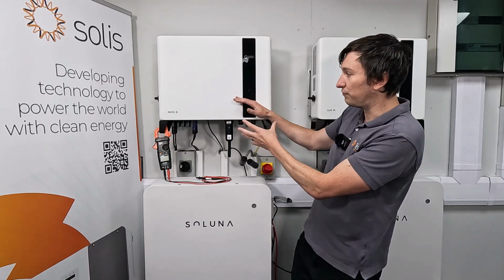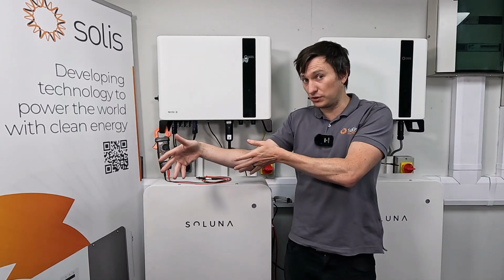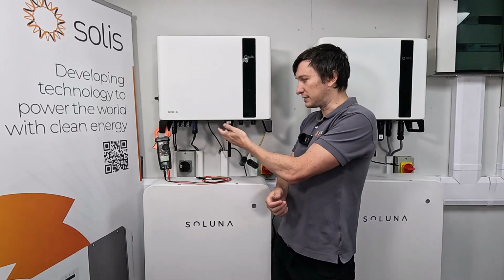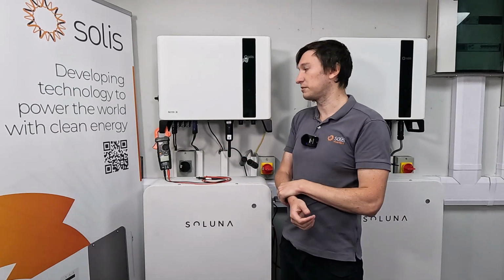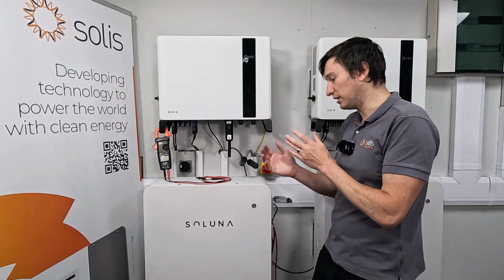The inverter is off, right? If I had a completely off-grid system where I couldn't get AC voltage, and the sun wasn't shining because it was nighttime when I installed the inverter, I'd need to turn on the inverter to finish the commissioning. You just start the battery, but it won't start up unless it's getting CAN communications, and it won't get CAN communications because the inverter's off. So you need to black start the battery.